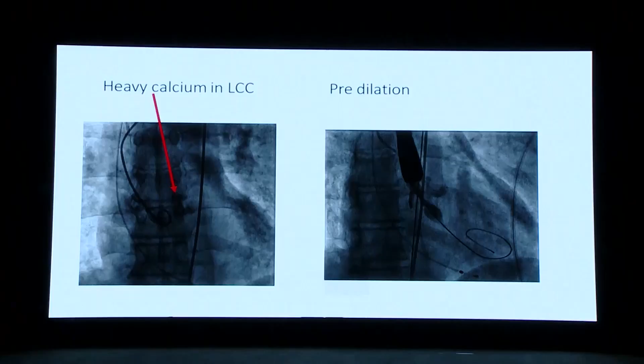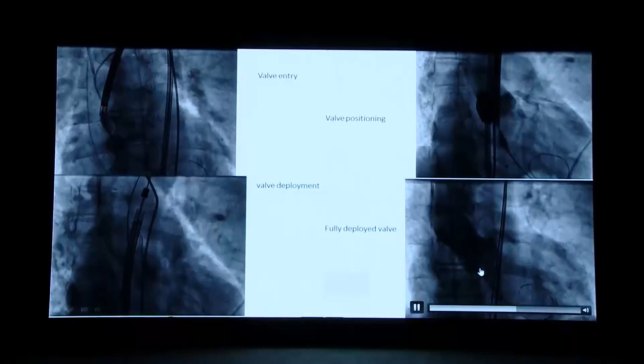Then we took the Evolut R valve and positioned it. Again in this case, we can point out the inflow of the valve is narrow. It is on the left side. Now the inflow of the valve is very narrow. It is not open. The same problem again, where because of the calcium, the valve is not fully open.